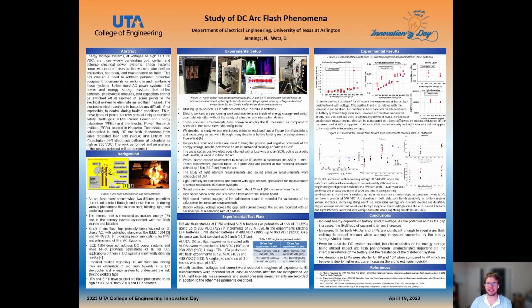From the valve-regulated lead-acid batteries studied at EPRI and UTA, the results we have are shown here. Starting off with the incident energy, for the incident energy produced from VRLAs, it shows it's very insignificant. However, one result did have a 1.6 cal per centimeter squared incident energy released. Often in the discussion of incident energy, there is a term used, arc flash boundary. This arc flash boundary is calculated in IEEE 1584 and NFPA 70E. This is defined as 1.2 cals per centimeter squared and is associated with the incident energy required to incur second-degree burns on the worker or someone who is present in front of the arc.